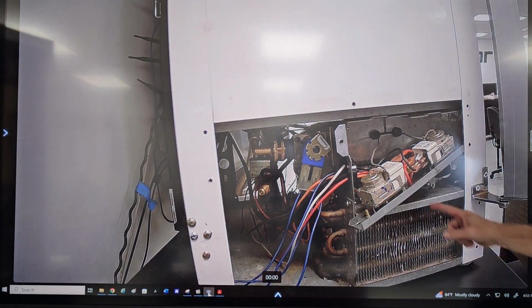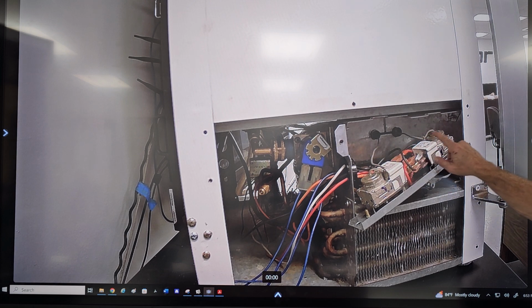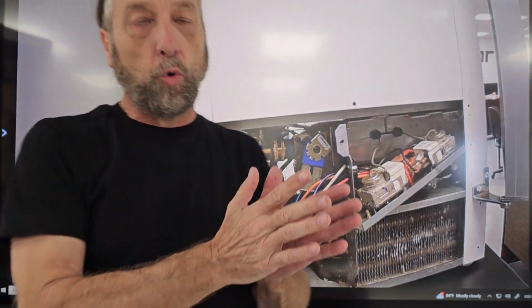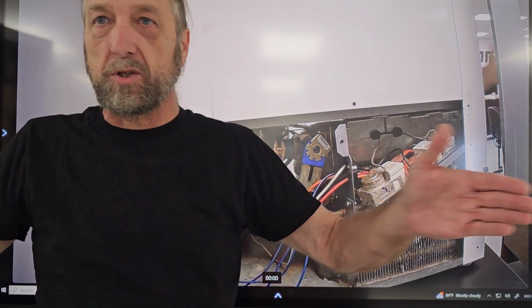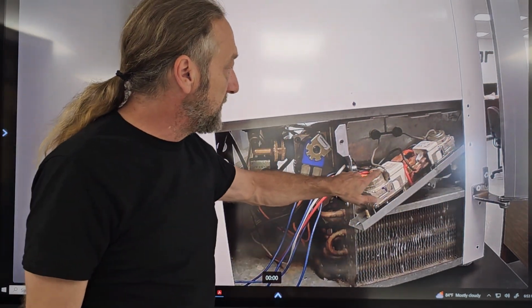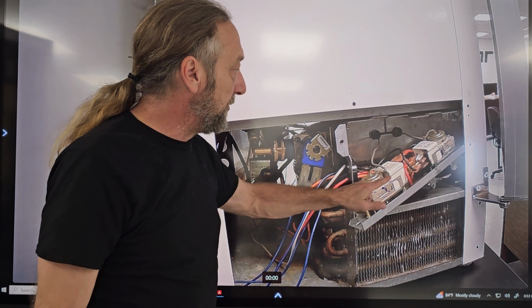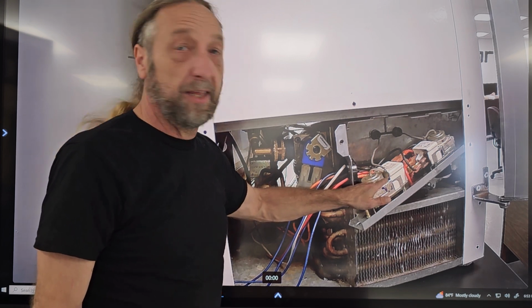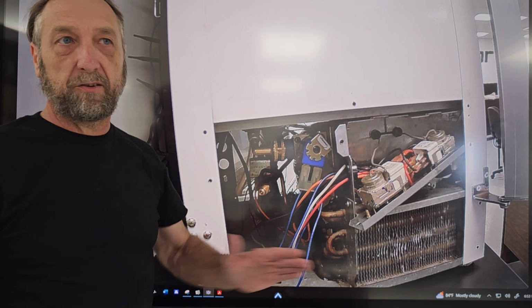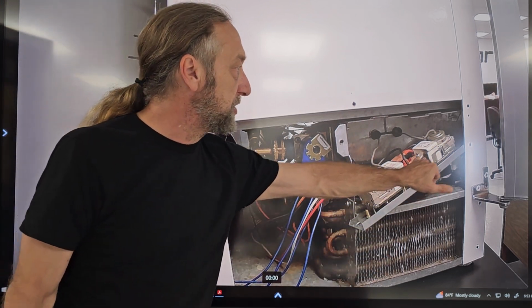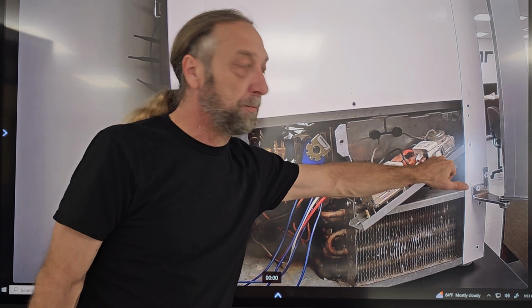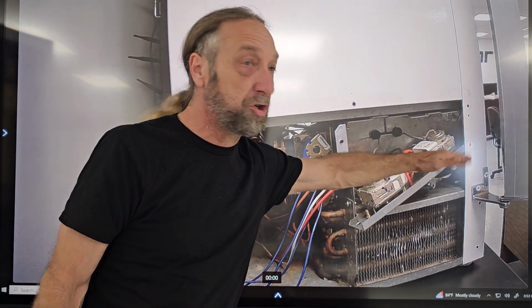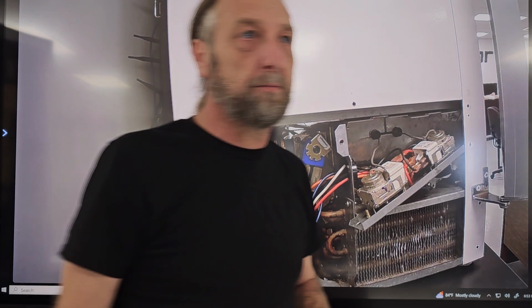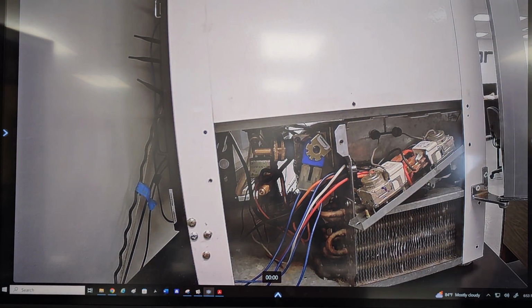So both of them have these capillary tubes running through here, and those capillary tubes are either filled with a liquid or a gas, and when it's heated or cooled, that gas expands or contracts, which cycles the switch. That's what these little bellows are. There's a little diaphragm or disc there that when it expands or contracts, pushes an actual switch contact. The switch contact is inside this ceramic piece, and it has a lever that's pushed by that capillary action. Okay, so that's that.